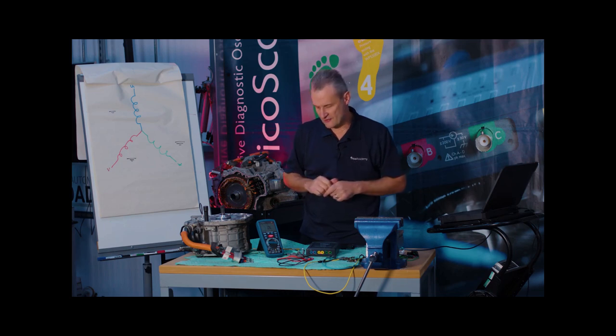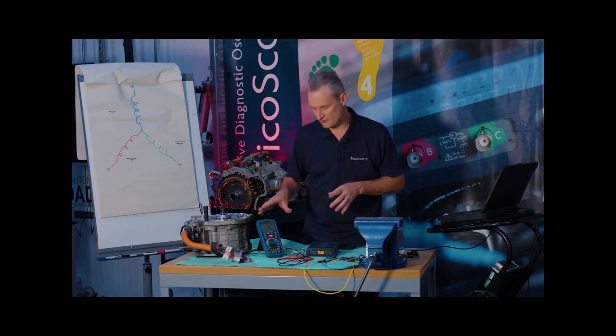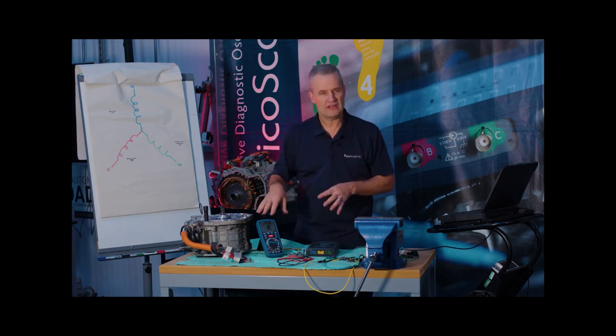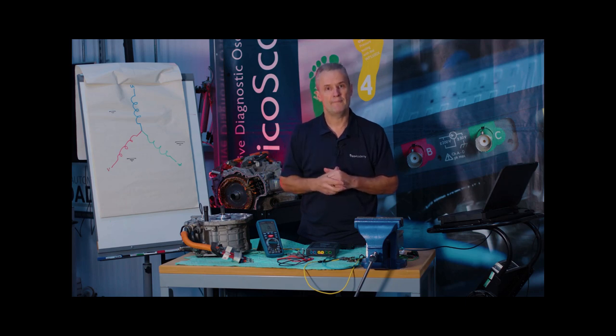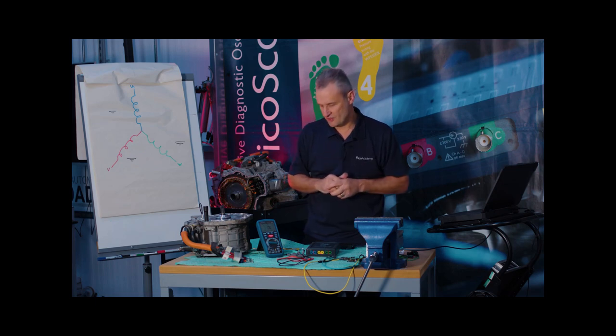What I really want to highlight is the limitations of using a conventional multimeter for this measurement. By no means is it redundant — it's a perfect tool for continuity and accurate measurements from zero ohm all the way up to mega-ohm. But when you start to drop below one ohm into the milli-ohm region, this is where we can sometimes have an issue.